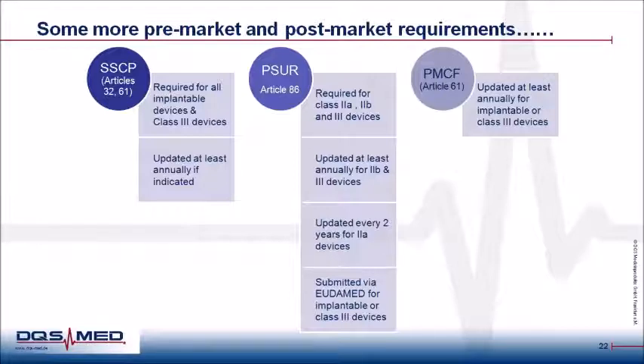The specific requirements for the SSCP can be found in Article 32 of the MDR. In addition, the European Union has also released the so-called MDCG paper 2019-9, Summary of Safety and Clinical Performance, a guide for manufacturers and notified bodies to provide guidance on presentation of the content and validation of this report. This guidance document outlines the minimum content required, and the manufacturer is thereby encouraged to include additional information to enhance the reader's understanding of the device's safety and performance.